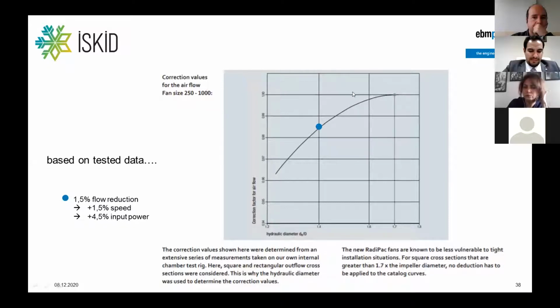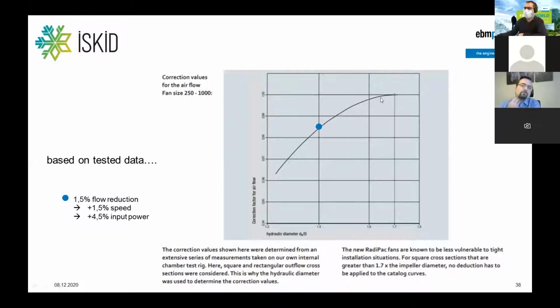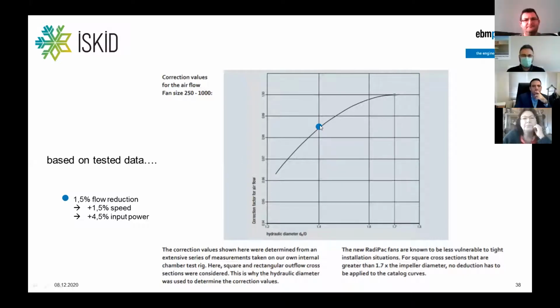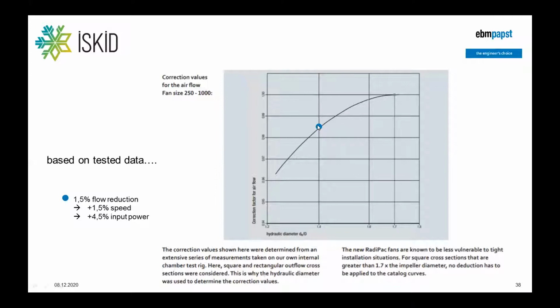You see, you have no losses. So this is a correction factor of 1. So there are no losses. When the overall dimension, the area where the air passes, gets smaller, let's say down to 1.4 times the diameter, we have about 1.5% of flow reduction. This means to overcome this, you have to increase the speed by 1.5%, and that results in about 4.5% of increased input power. And this could be documented in the software.